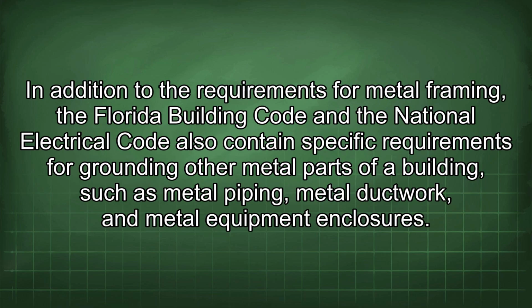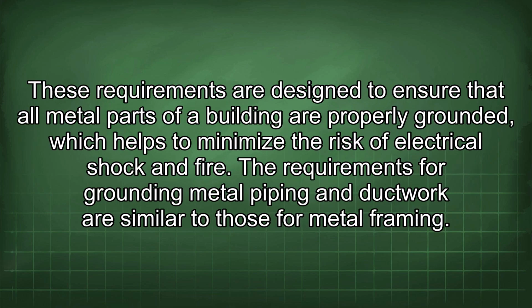In addition to the requirements for metal framing, the Florida Building Code and the National Electrical Code also contain specific requirements for grounding other metal parts of a building, such as metal piping, metal ductwork, and metal equipment enclosures. These requirements are designed to ensure that all metal parts of a building are properly grounded, which helps to minimize the risk of electrical shock and fire.